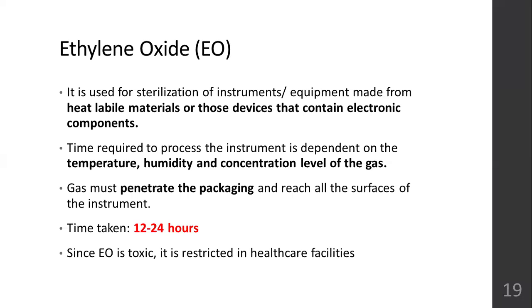The time required to process the instrument is dependent on temperature, humidity, and concentration level of gas. And the gas that we use here should penetrate the packaging and reach all the surfaces of the instrument. Otherwise, sterilization is not achieved. So time taken is around 12 to 24 hours. And since ethylene oxide is toxic, it is restricted in healthcare facilities. But pharmaceutical companies and all, you can use ethylene oxide gas.